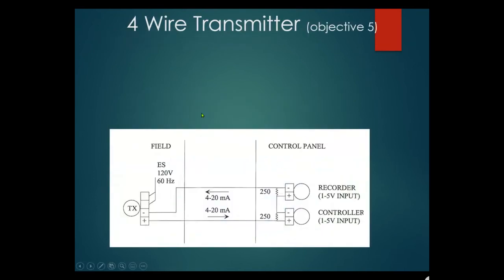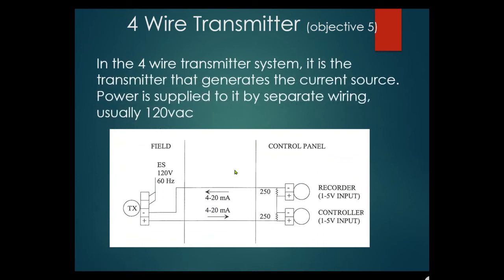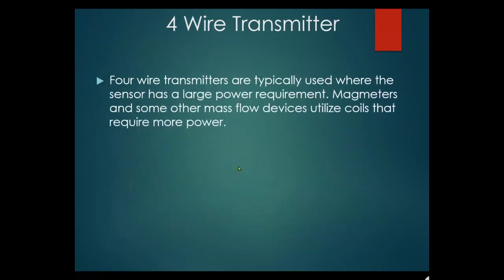Objective five — four-wire transmitter: in this case the loop has a separate voltage supply (such as 120V 60Hz or 24V DC) for the transmitter power, separate from the 4 to 20 milliamp signal wires. Four-wire transmitters are typically used when the sensor has a large power requirement — mag meters and some mass flow devices that utilize coils requiring more power.